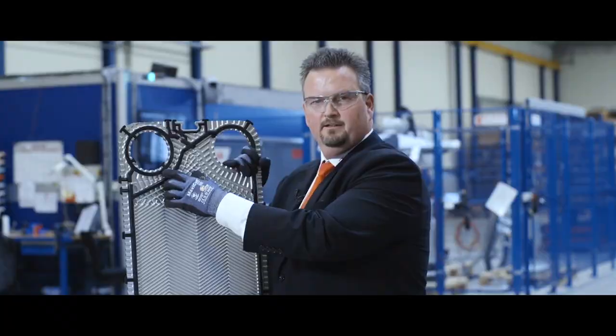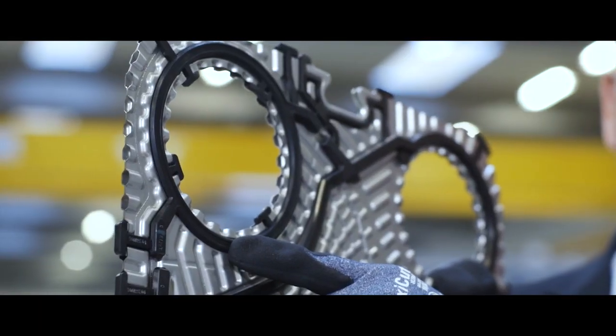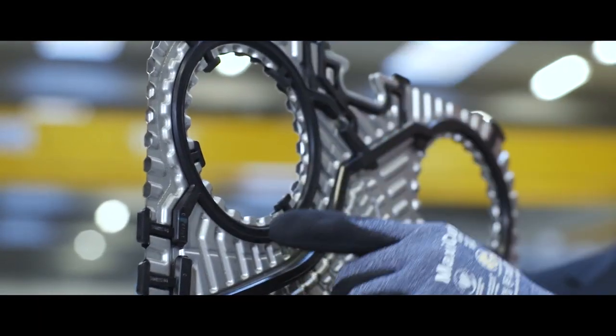Also the ring gasket here is chosen based on what refrigerant is used, but also what oil is used in the refrigerant. This is done to make a better sealing on the cooling system.